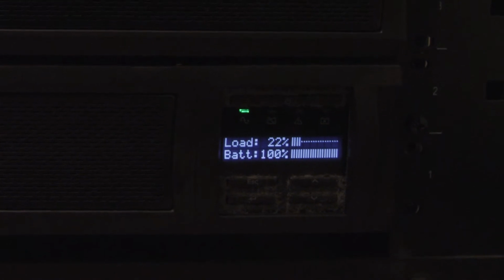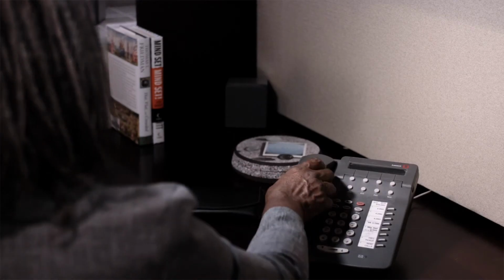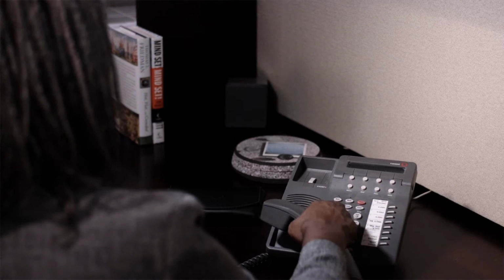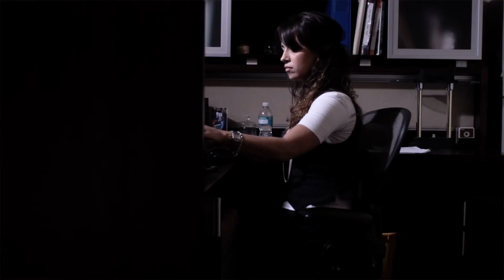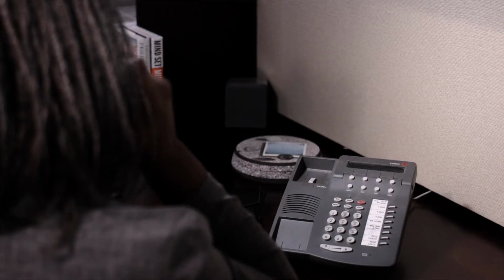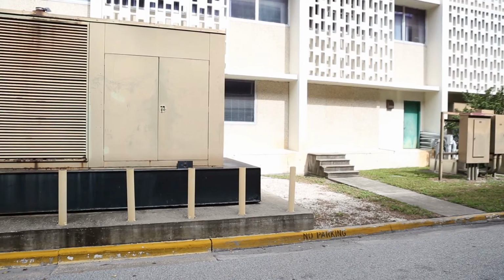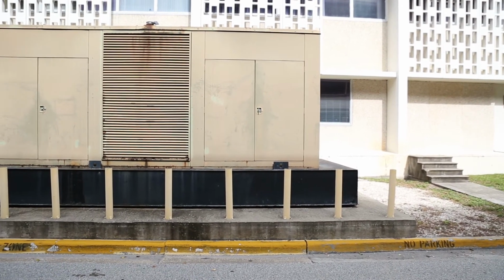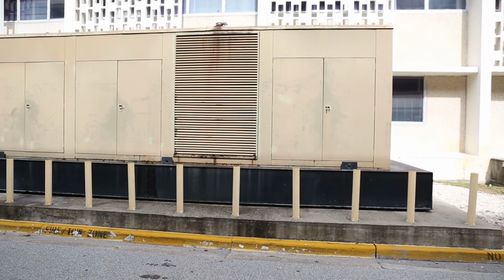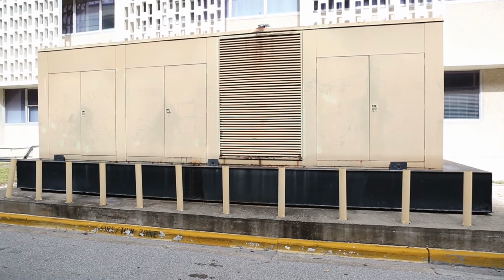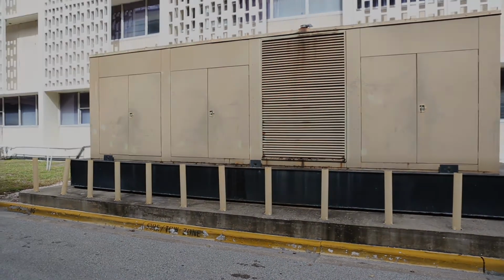In buildings utilizing voice over IP for telephony, we are required by university policy to run the network for at least 90 minutes during a power failure. This allows phones to continue operating for emergency calls. Many of our buildings have backup generators that will automatically start after power has failed. But we still need UPSs to get us through the brief outage while these generators start.